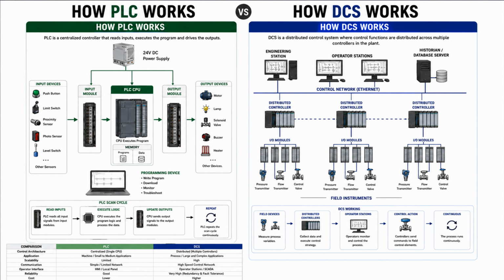PLC versus DCS comparison. Now let's compare both systems directly. A PLC is usually centralized. A DCS is distributed. A PLC is ideal for individual machines. A DCS is designed for complete industrial processes. PLC systems are easier to install. DCS systems are easier to expand. PLCs usually cost less. DCS systems cost more, but provide much greater redundancy, higher availability, and better plant-wide monitoring. Neither system is universally better. The correct choice depends entirely on the application.